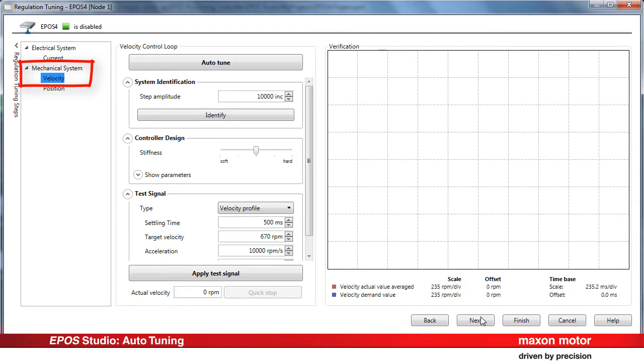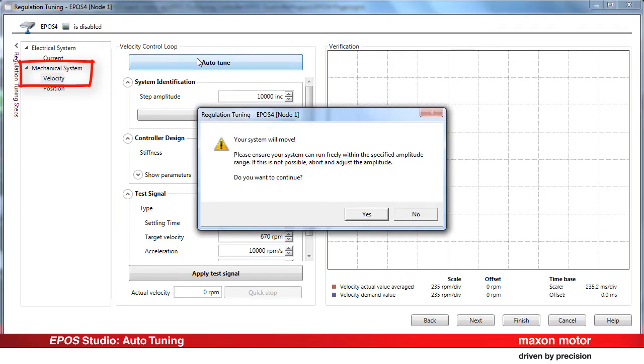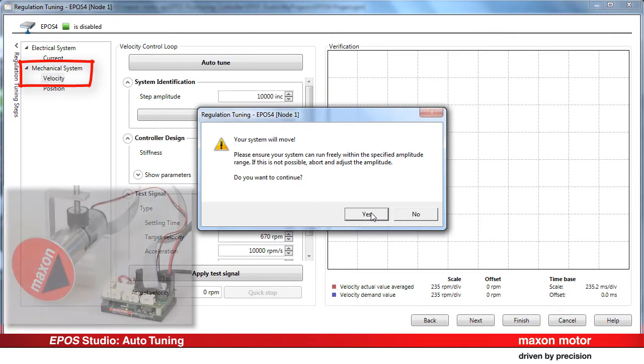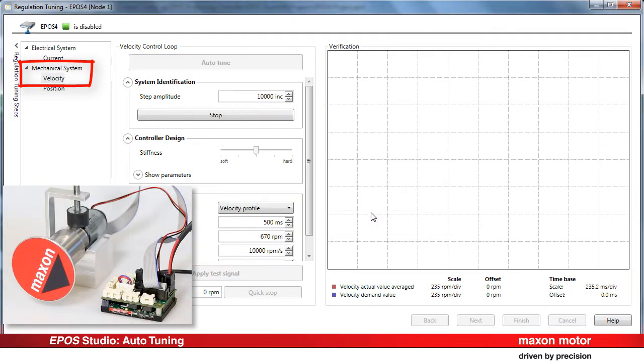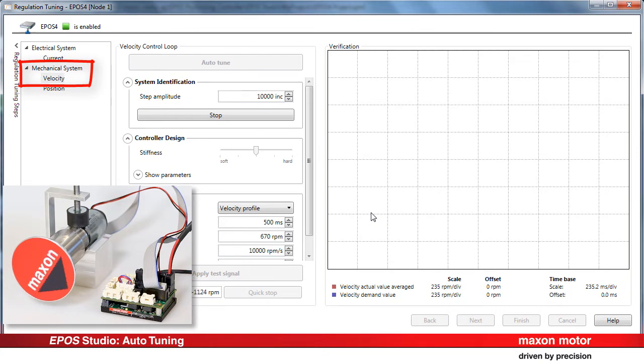Now we repeat the procedure with the velocity control loop, the first part of the mechanical system response. Just press the autotune button. Make sure that the system is free to move and continue. The tuning process performs an identification of the mechanical plant and calculates relevant control loop parameters.